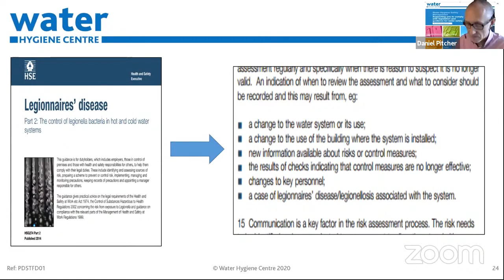Water safety isn't just about Legionella - there are other risks to consider. For example, if we use temperature control to manage the risk of Legionella growth by keeping hot water at 60 degrees C, we now have a scald risk.